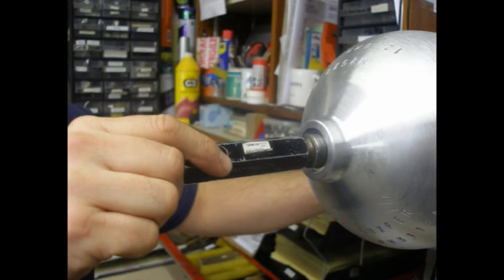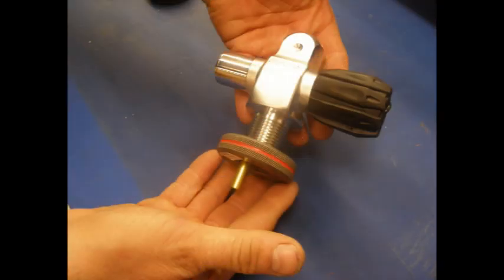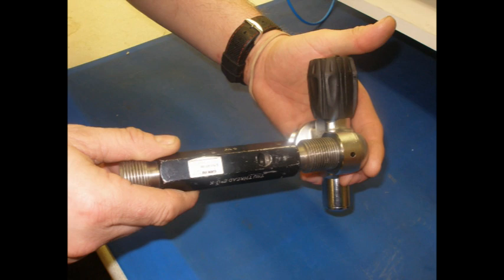As I'm sure most of you know, the thread gauges are used for a number of things during the inspection and testing of diving cylinders and valves. It's certainly used for the neck thread on the cylinder, and then for the stem of the valve, and of course the outlet port for the valve as well, the G5/8. So now let's look at what the various types are.